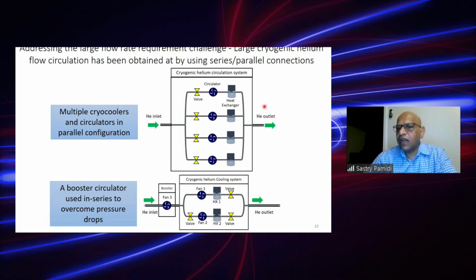This system allows us to get large flow rates, but the pressure drop it can handle is the same, because they are in parallel. It can only handle so much pressure drop. By putting systems in parallel, you get more flow, but the pressure drop capacity will still be the same. But if you want a larger system to fight the pressure drop in the application, you may have to think about two fans in parallel, and another fan in series. We call it a booster fan. This is primarily to have more capacity to handle pressure drop. Applications, superconducting cables or motors, generators themselves, generate significant pressure drop. Unless you have a system that can handle the pressure drop, you will not be able to get large flow rates. So this parallel and series combination is what is needed depending on the application.